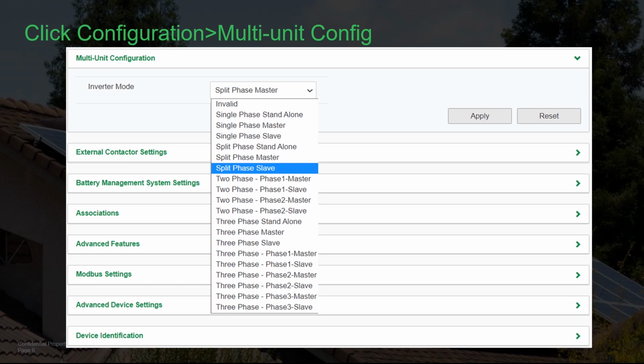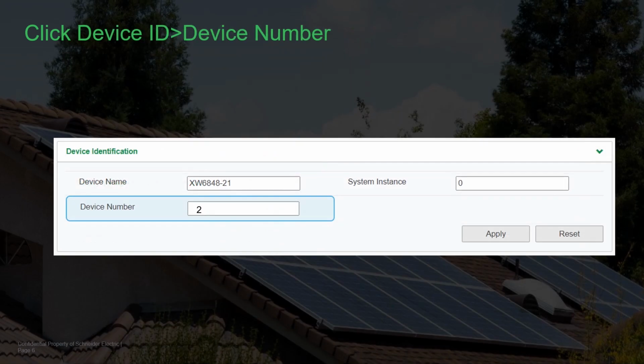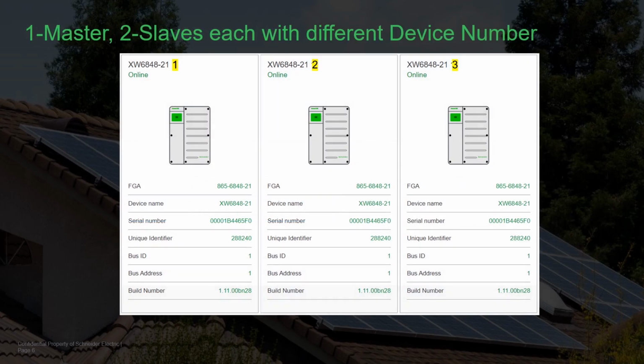We typically only use split-phase and three-phase options. Next, navigate to the device identification section and select device number 2 for the first slave and number 3 for the second slave, and so on. Numbering is irrelevant provided each XW Pro has a different device number, and then click Apply. Once you've programmed for multi-unit operation, it's time to set the system up for how you intend to use it.